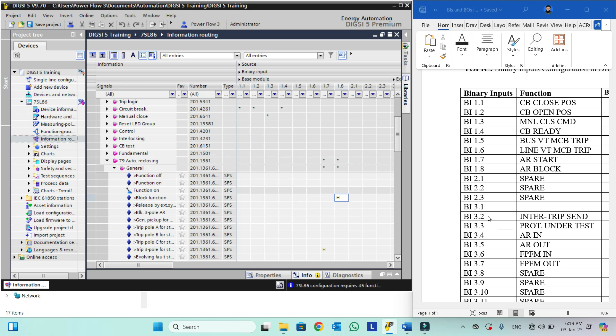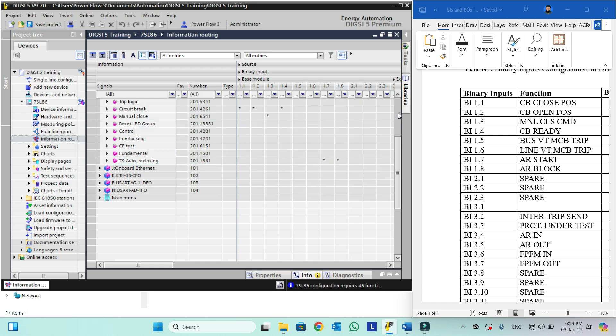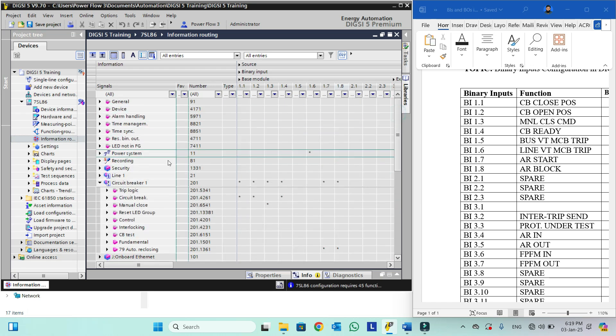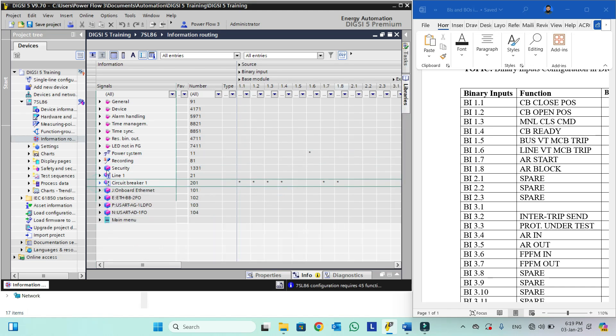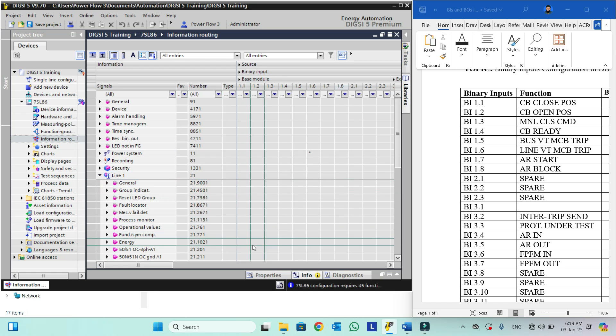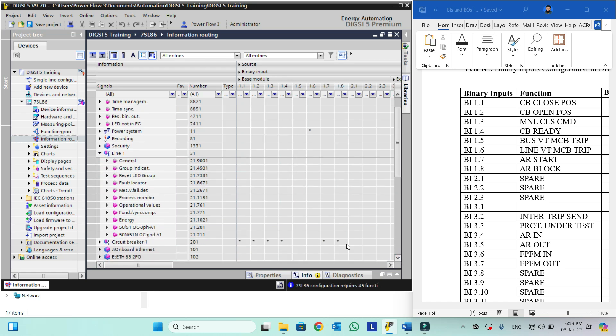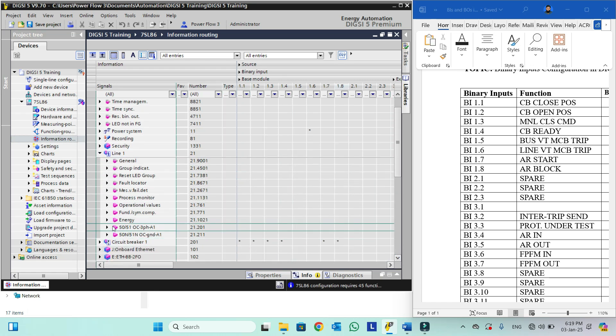Binary input 3.3 is protection under test — it means when this binary input is active, certain protection should be blocked. In this case we will go into line, then into any function we want to block, open it, and block it.